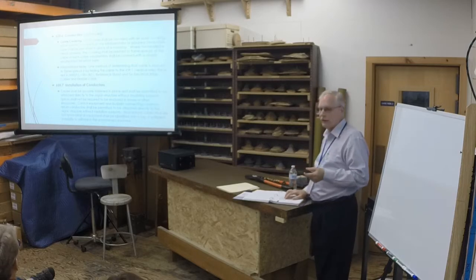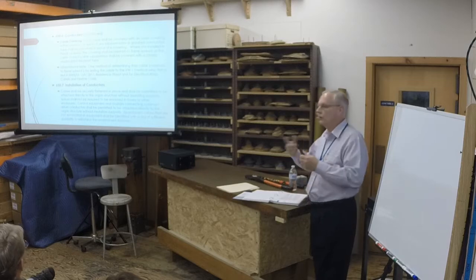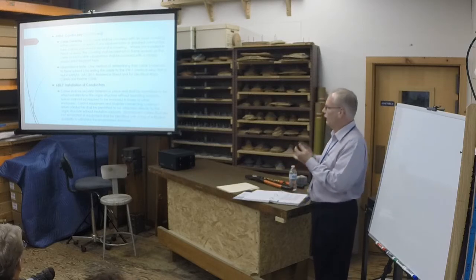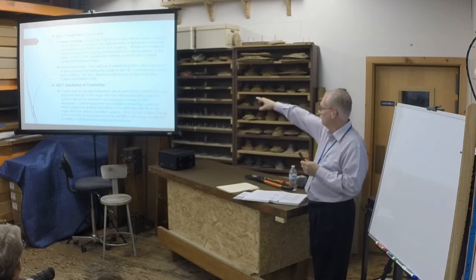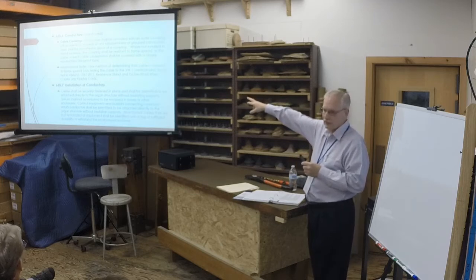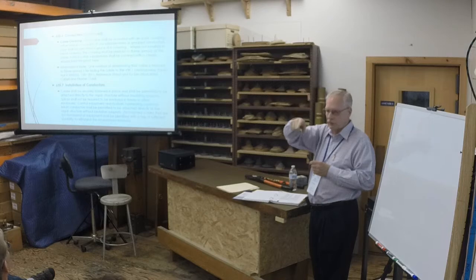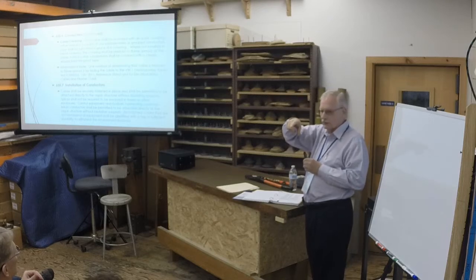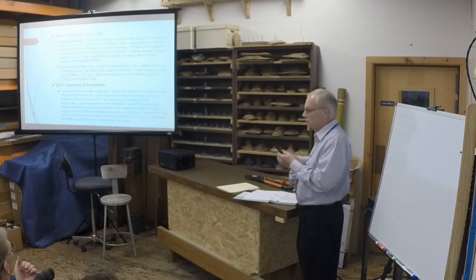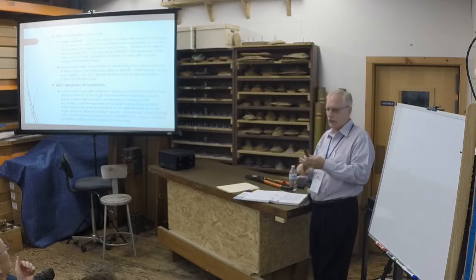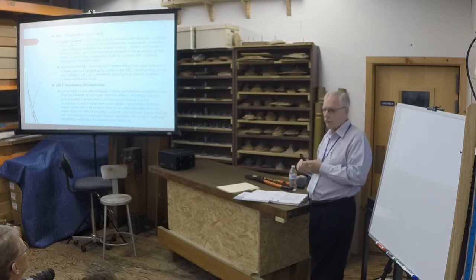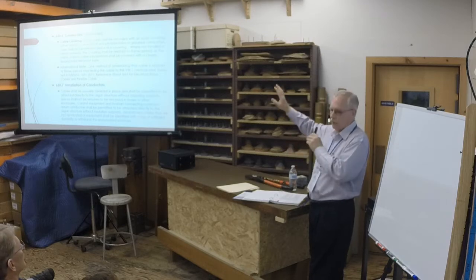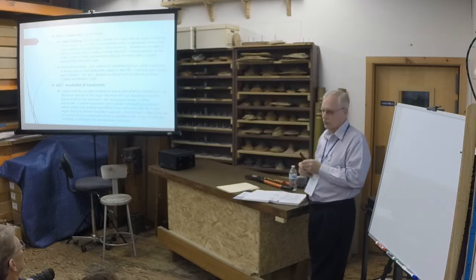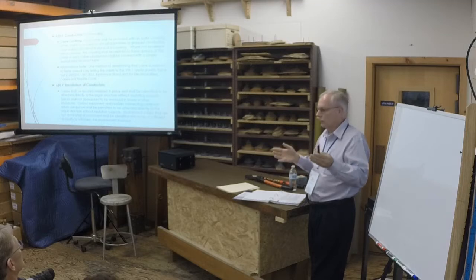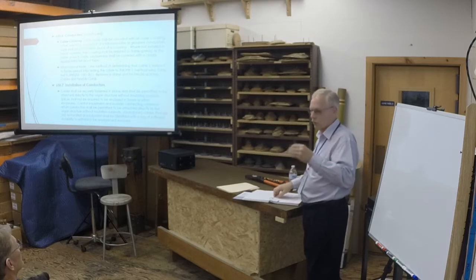Tape shall be permitted in lieu of covering, so you can continue to use your tape, as long as it complies with the flame retardant standards. The product OSI sells complies with that. Scotch 88 tape complies with that, though God help us, nobody wants that in an organ. There are friction tape products that also comply. Make sure you have a product that complies. At one point OSI was selling more than one version, one was and one wasn't compliant. This goes way back.